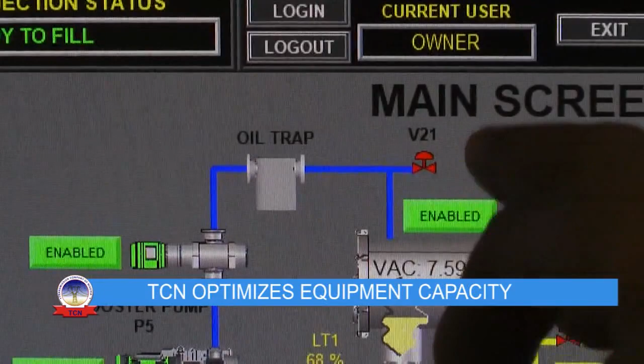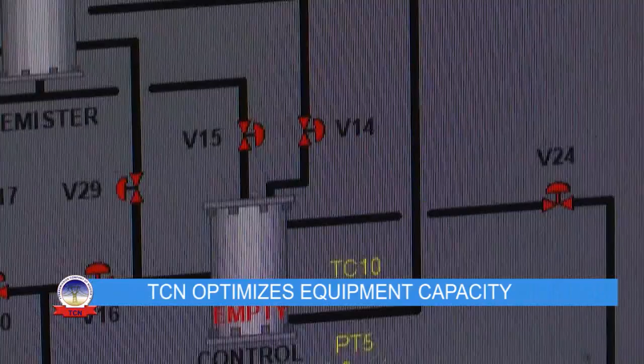The process will continue every day until the oil is okay, before we shut down for a period of 4 weeks minimum. The benefit of this regeneration is, number one, the lifespan of the transformer will increase, and its capacity will increase again to perform - where it was lower, it will increase to the highest. And after this regeneration, the maximum lifespan extension they can achieve on this transformer is 10 to 15 years later.